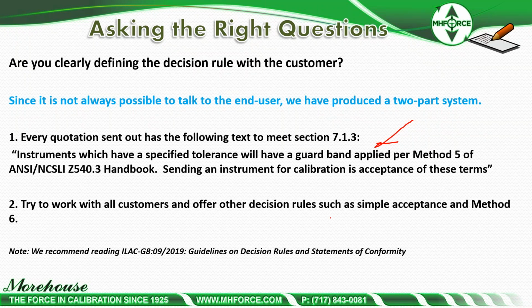If we send a quote and someone doesn't know the decision rule they want, we're defaulting back to method 5, which is taking the measurement uncertainty into account and just subtracting it. There's other methods. There's method 6, so many different ones. I just recommend, it's a free document, reading ILAC-G8:09/2019, Guidelines on Decision Rules and Statements of Conformity.